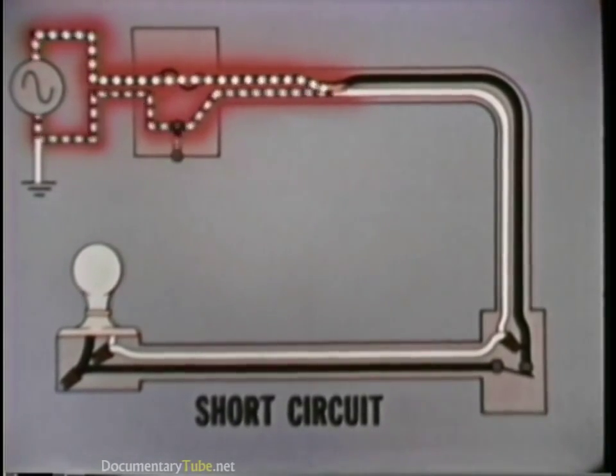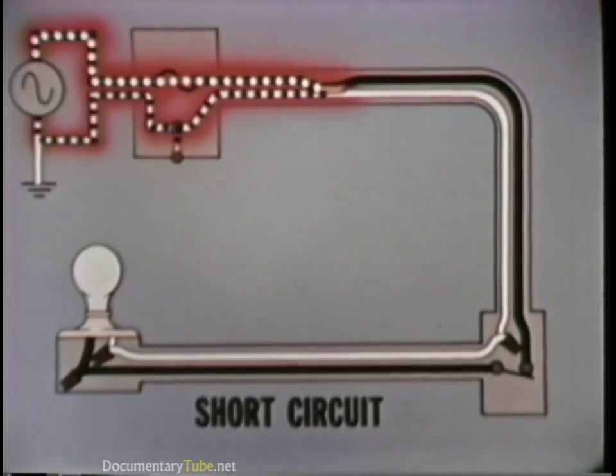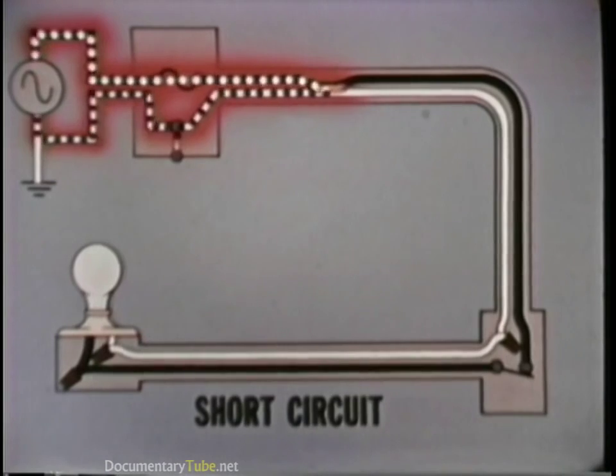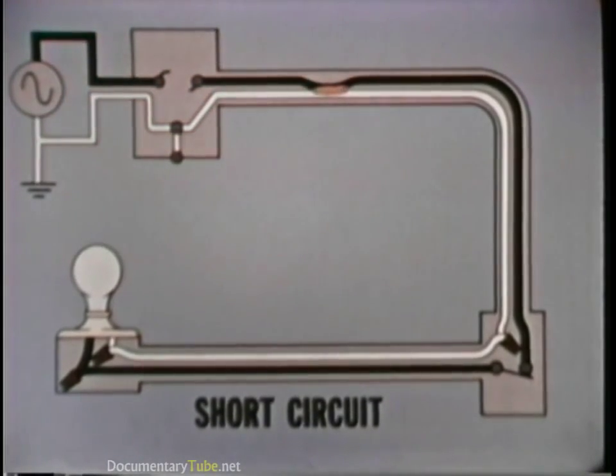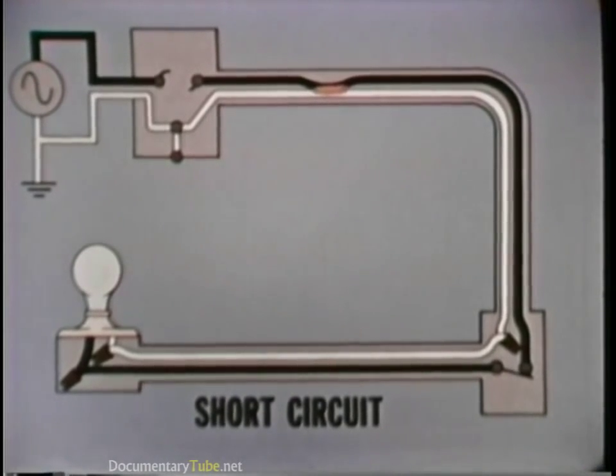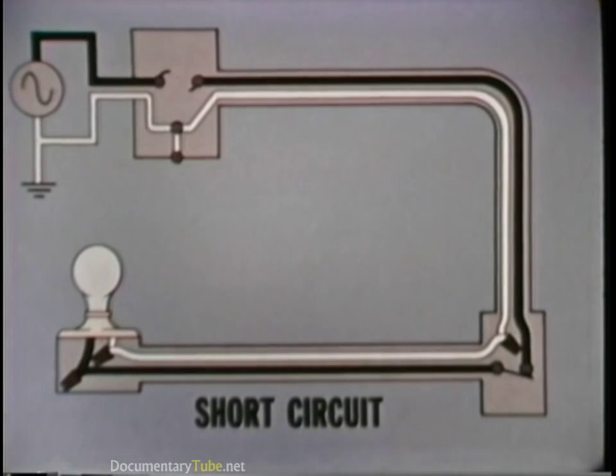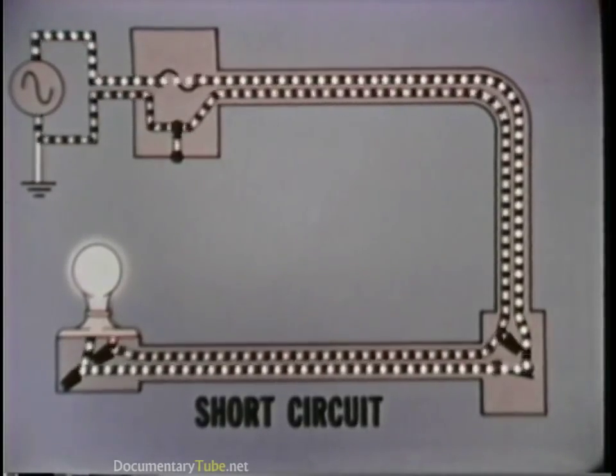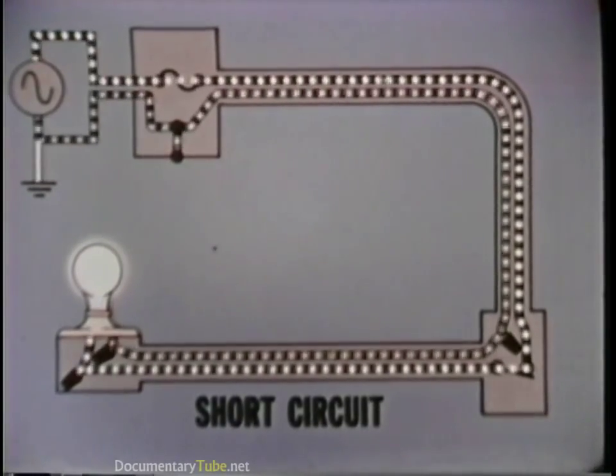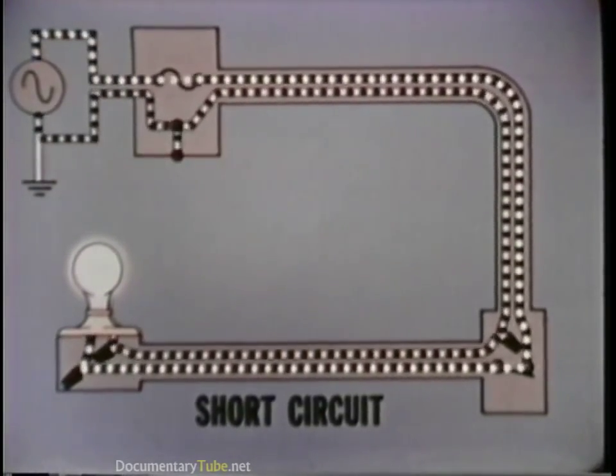However, since the circuit is properly protected, the fuse or circuit breaker reacts to the excessive current and blows or trips, stopping the current flow. To correct the short, the damaged wires must be separated and in most cases replaced. Then, replacing the fuse or resetting the circuit breaker restores the circuit to normal operation.